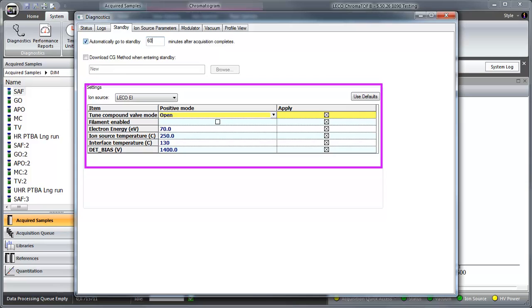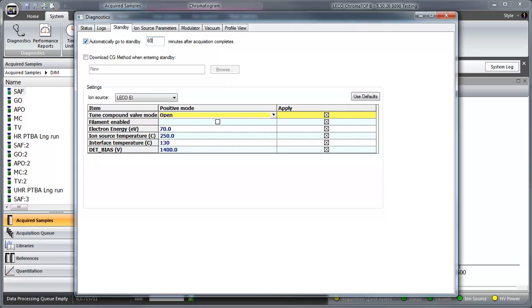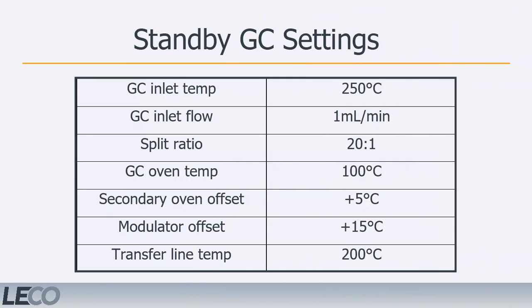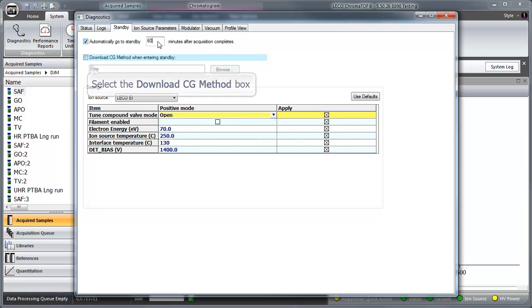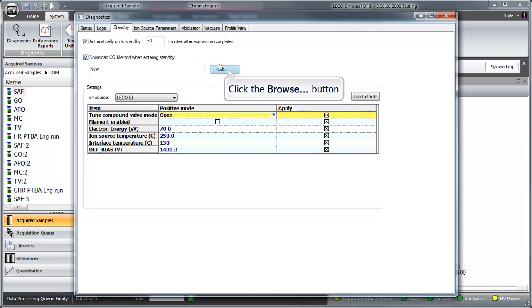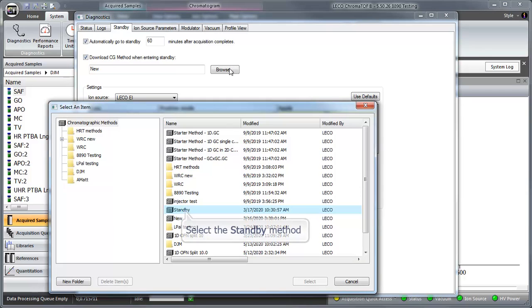Specific settings can be changed in the table below. LECO's recommended standby settings for each source type are provided as default settings. The GC standby method is optional and can be used to preserve the carrier gas. To enable a GC standby method, first create a GC method with the following settings. In the Standby window, check the GC method box and use the Browse button to select the newly created Standby GC method.